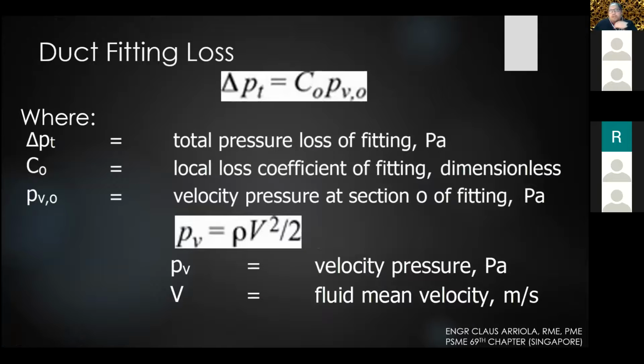So if you are going for the duct fitting loss, which we usually can find in SMACNA, okay, SMACNA says that the total pressure loss of the fitting is equal to the local loss coefficient of the fitting, which is dimensionless, times the velocity pressure at the section of the fitting, which is in Pascal. Then the velocity pressure is equal to the density times the fluid mean velocity squared, in meters per second, over 2.